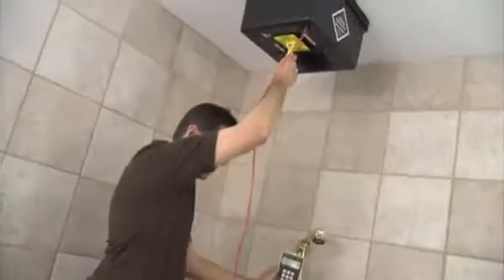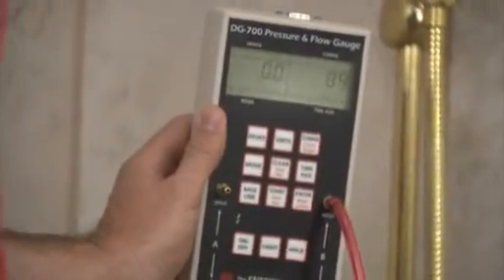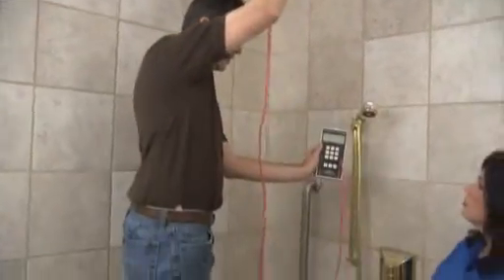This simple tool demonstrates the cubic feet per minute rate, also known as CFM, showing how much air is actually sucked out of the space. Brad uses an exhaust fan flow meter to measure the CFM and verify the fan is running at its rated level. It's flowing at a little over 80 CFM, and it's an 80 CFM rated fan. The contractor who installed it performed a ventilation calculation to determine that exactly 80 CFM was the proper amount needed to exhaust air from the space.